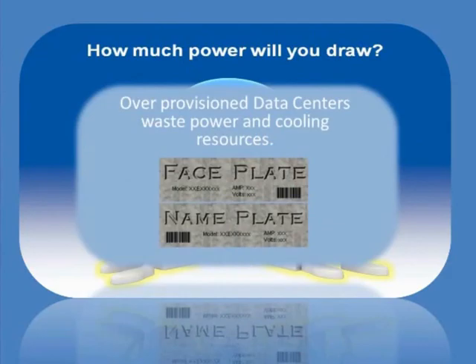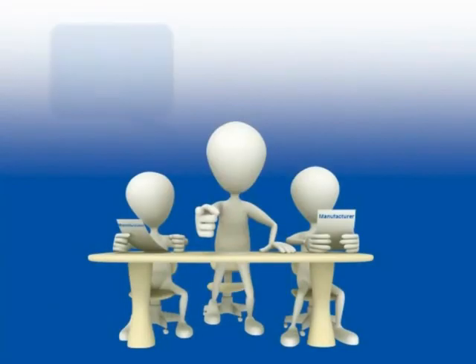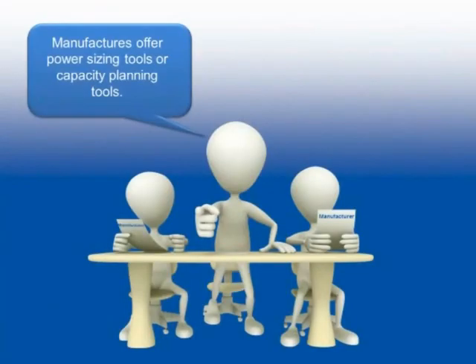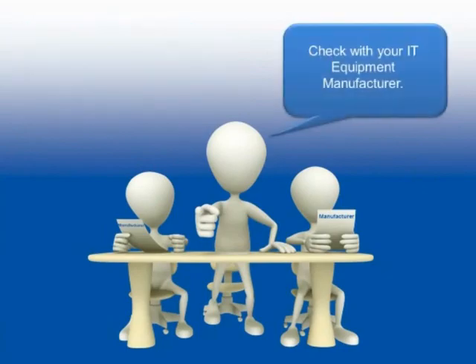When you use faceplate power, you can over-provision a data center, wasting valuable power and cooling resources. Most manufacturers offer a power sizing tool or capacity planning tool for true power measurement. Check with your IT equipment manufacturer when calculating your amperage draw.